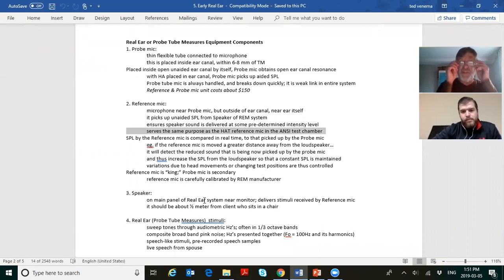And if you go back to your ANSI and you look in the PowerPoint slide that lays out the components inside of an ANSI test box, you'll see two mics. One mic is the mic that is attached to the 2cc coupler. That's like the probe mic, okay? That's what's measuring what's coming out of the hearing aid. The other mic is called a monitor mic, and it makes sure that the sound coming from the speakers is behaving itself, is doing what you said. It makes sure that the input into the hearing aid mic is what you stipulated. So that's why you calibrate an ANSI test box in the morning too, to ensure a flat frequency response.